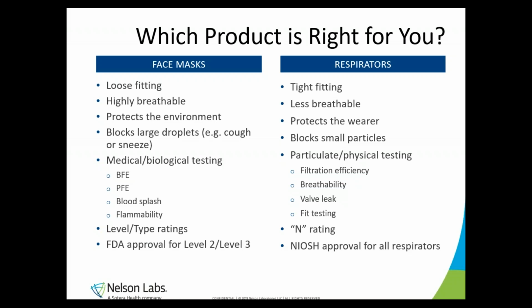These types of products require medical and biological testing, which includes bacterial filtration efficiency, particulate filtration efficiency, blood splash, flammability, and other tests. They have level and type ratings, and here in the US, level 2 and level 3 masks require FDA approval.